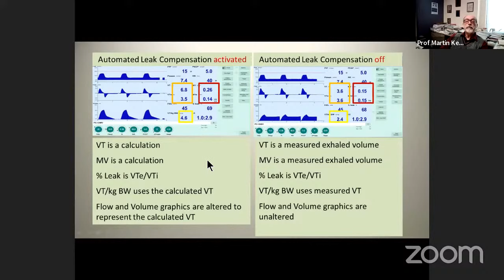With leak compensation activated, despite the same very large leak, you now are measuring the exhaled tidal volume differently. You're using the calculated value, okay? The measured tidal volume is still the same, but the actual tidal volume that the device tells you the patient is actually seeing is a normal 4.6 per kilo. What I don't like is that the waveform eliminates the visual illustration of the leak. I would like to have that independently be turned on or off, but this is important. So the calculated tidal volume works remarkably well, and it corrects even very, very large leaks.